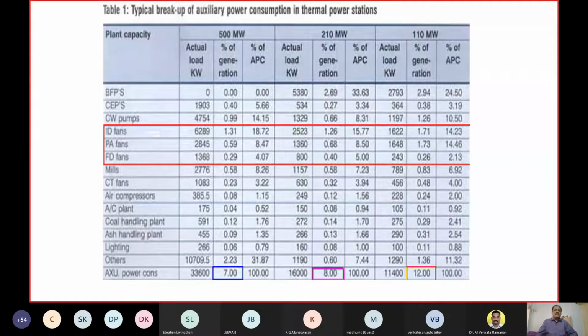If you look at the energy consumption in power generation, the typical breakup of auxiliary power consumption, there are three classical examples taken here: a 500 megawatt generating station, a 210 megawatt generating station, and a 110 megawatt generating station. If you go down and look at this auxiliary power consumption, approximately 7% is the benchmark for a 500 megawatt power station, 8% is the benchmark for a 210 megawatt power station, and 12% is the benchmark for a 110 megawatt one. What are the loads? ID fans, PA fans, FD fans. There are also other loads: ash handling, coal handling, conveyors, and so on. So typically, electrical motors, out of the 8%, will contribute almost 70% of the total energy consumption, even in the case of auxiliary power consumption.